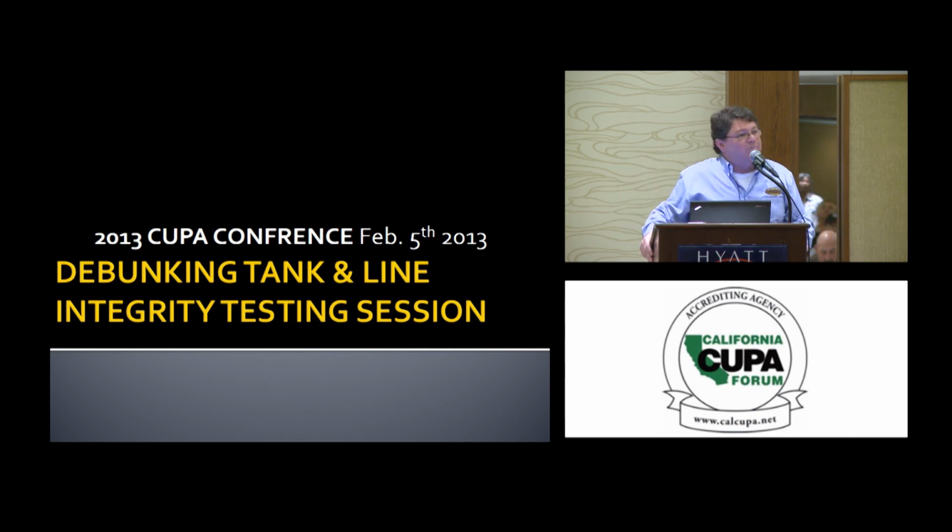If you have an owner and operator with an ATG that's giving him erratic readings, have him change his level for the test. And I have Veeder-Root in the audience. I know for a fact they can find very small leaks if they extended the test time on a tank. Okay? If it's a problem tank, extend the test time. Do more of a precision tank test. The Veeder-Root will find it if it's in the liquid portion. I'm not a Veeder-Root salesman, okay? But I know that the equipment used right will do its job.